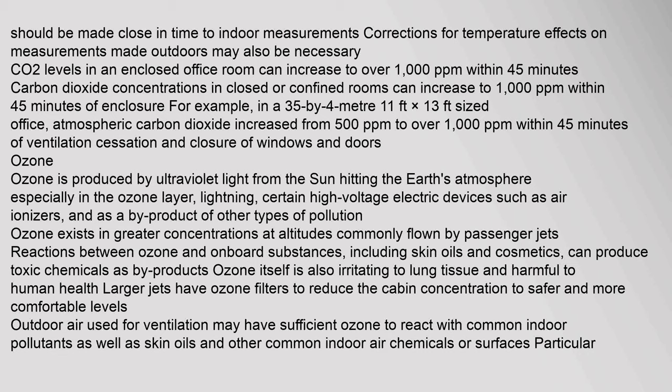Measurements of carbon dioxide for purposes of assessing ventilation adequacy need to be made after an extended period of steady occupancy and ventilation — in schools at least two hours, and in offices at least three hours. Portable instruments used to measure carbon dioxide should be calibrated frequently, and outdoor measurements used for calculations should be made close in time to indoor measurements.